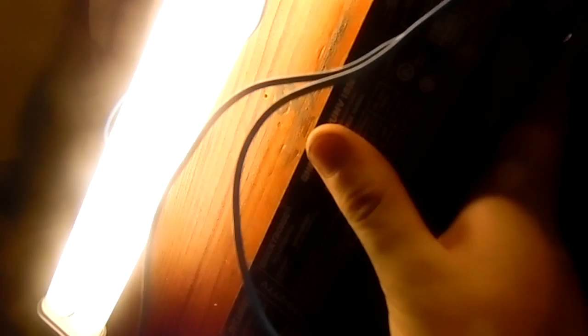If I come over here to my fluorescent ballast, you see a connection right here that's running into this heat shrink, which connects to the third prong on here. You always want to ground this out because you're dealing with high voltages here, and these things get hot. Well, not really hot, they get warm over time. That's because you're flowing so much current through it. Let me hook one of these up to show you guys. I'm going to be using this tube to hook up. You probably remember this tube from when I first made the videos.